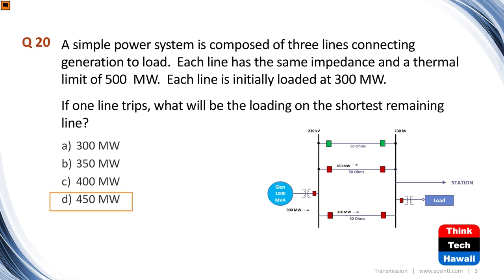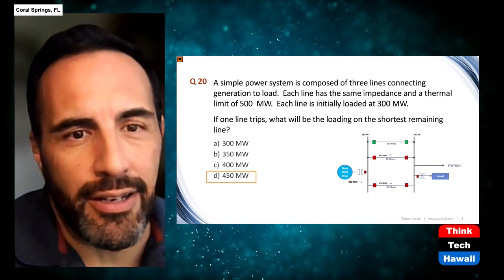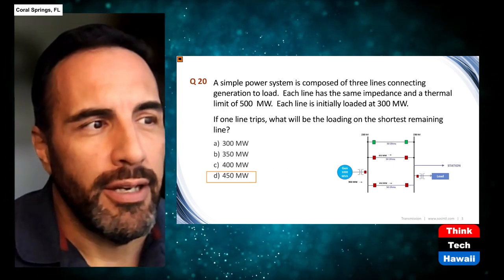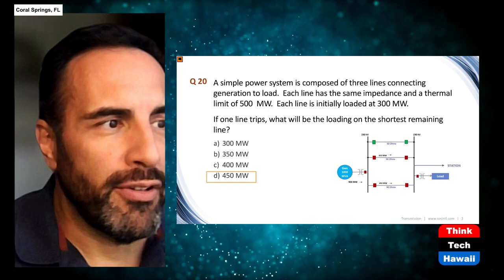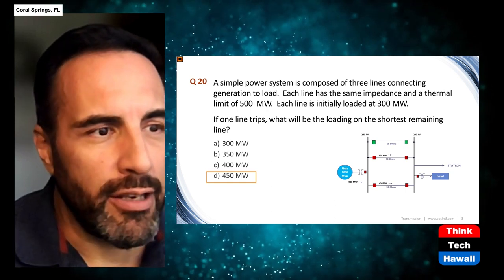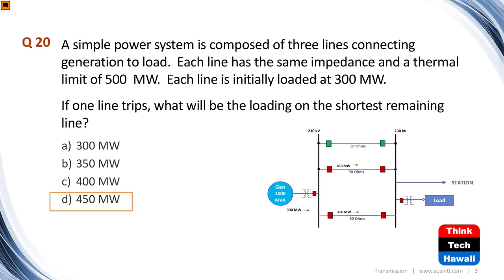If all the lines are in service, each line is loaded at 300 megawatts. With three lines at 300 megawatts each, that's a total of 900 megawatts flowing from the bus on the left to the bus on the right. You'll notice the generation shown below is Gen 1000 MVA, and they show 900 megawatts flowing.